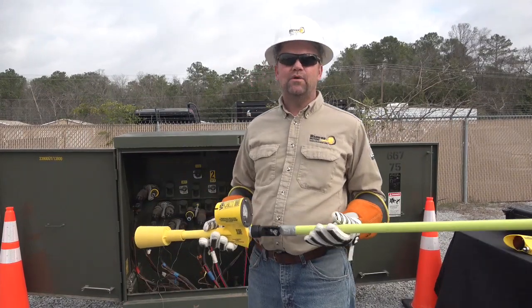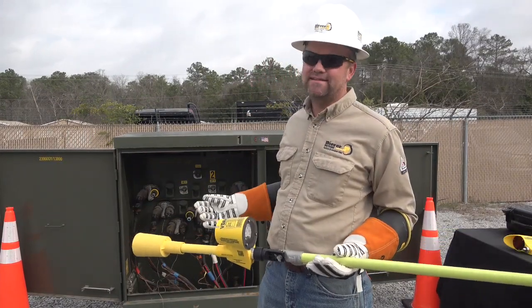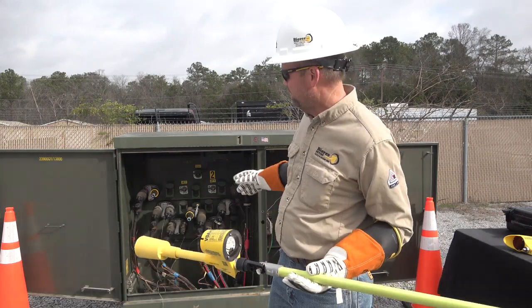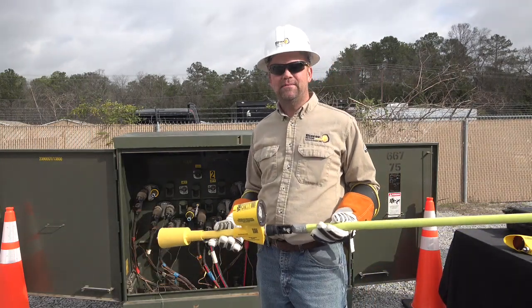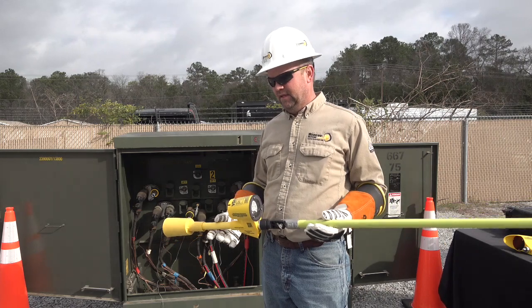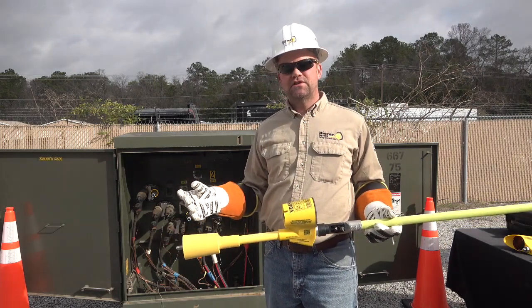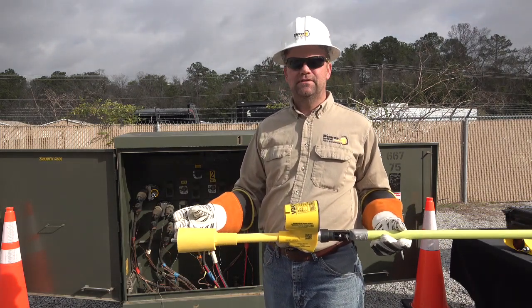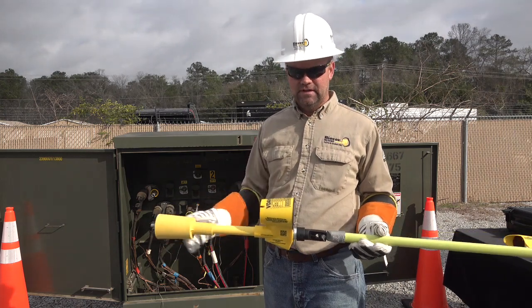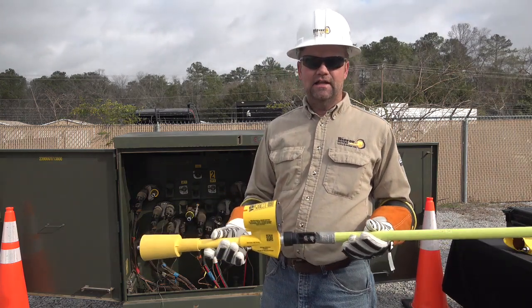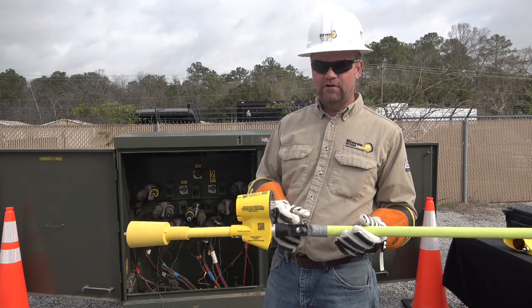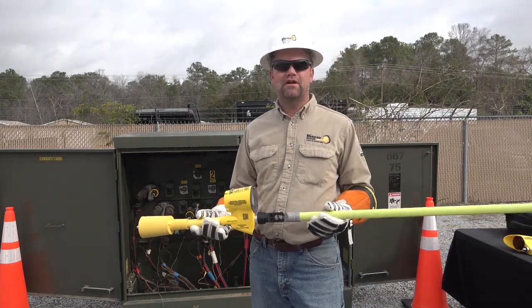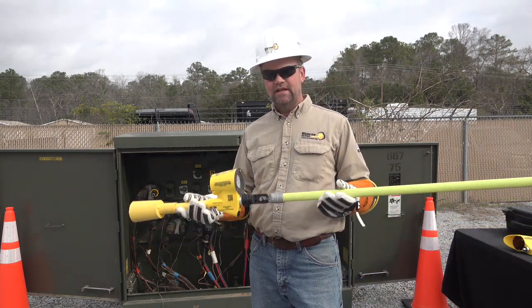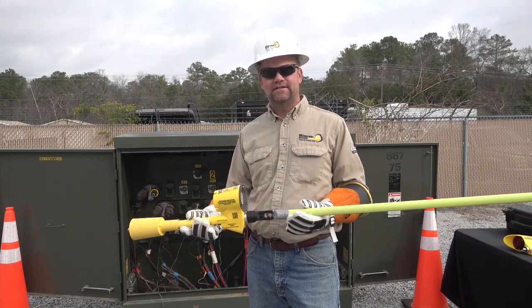Okay, now we're ready to go ahead and test for de-energized and energized. We have both scenarios going on here behind me on our pad mount transformer. And I have the proper accessories on here. So I have my bushing adapter threaded onto the end of the probe. I have my hotline tool adapter here, so I have my universal grip all adapter threaded onto my live line tool fitting, and a universal stick attached to that.